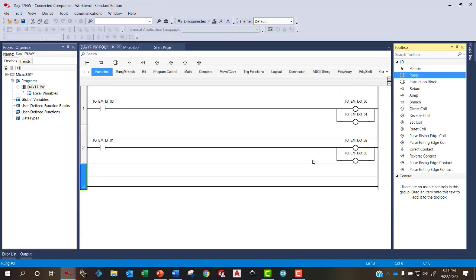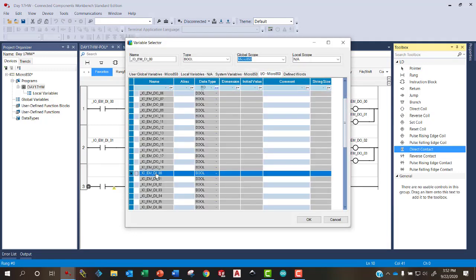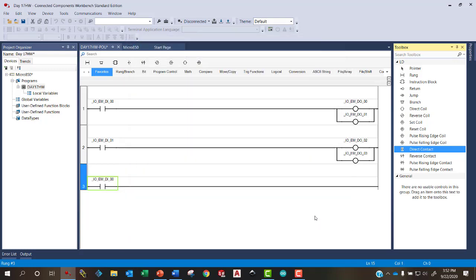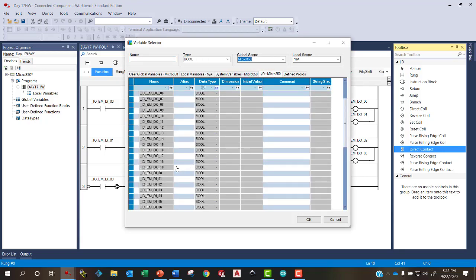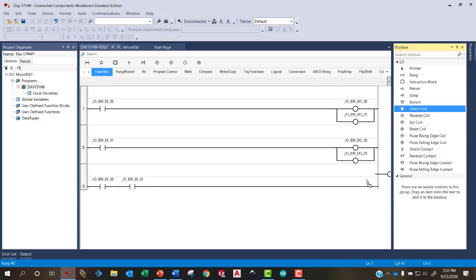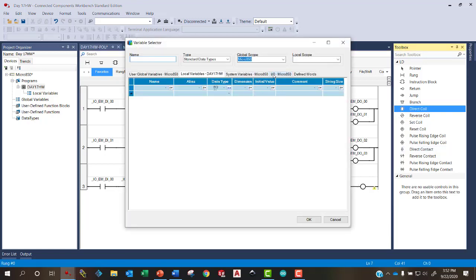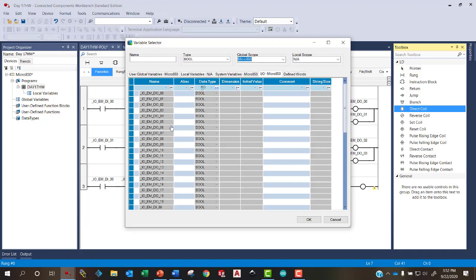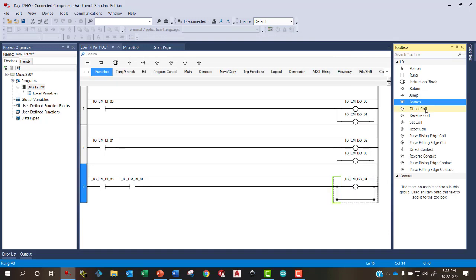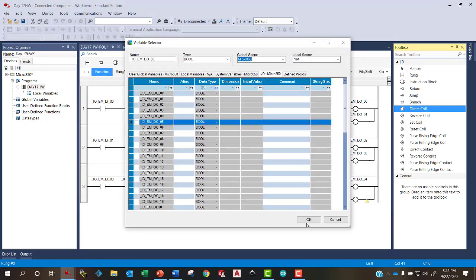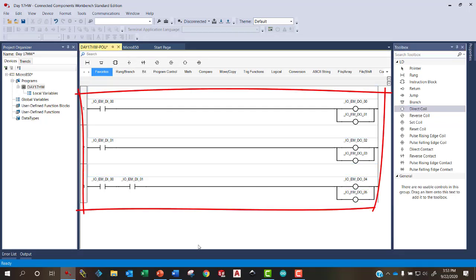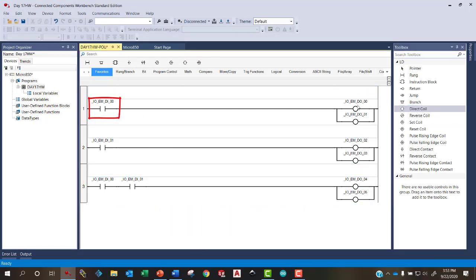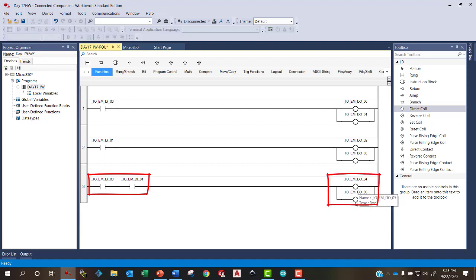So let's grab a new rung. And this time I'll grab a direct contact again. And this one is Digital Input number 0. And I'm now going to grab another direct contact and place it right after this one. And we'll connect this one to Digital Input number 1. So now the only way power can flow through this rung is if both of these are connected. And if both of them are connected, let's bring this direct coil and connect it to Digital Output number 4. And let's branch around it and bring in another direct coil and connect it to Digital Output number 5. So now as this scans through this rung, if this one is connected, both of these will energize. And if this one is connected, both of these will energize. And if they both happen to be connected, these two will also energize.